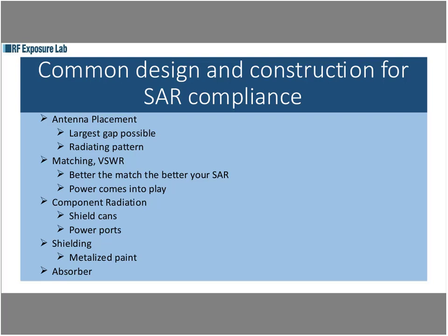Your VSWR, the better your match, the better your SAR. If you've got a really poor match, your SAR value will go up with the mismatch of the VSWR. And then obviously your power plays into it. If you can reduce your power at all and still meet all of your other requirements, that always makes SAR a little bit easier to pass than if you have to make it at full power.